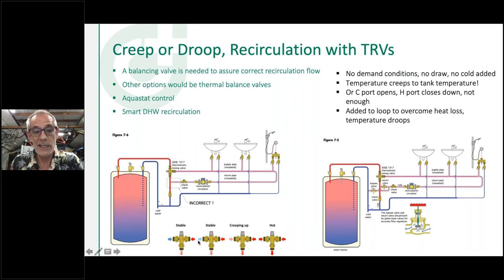Over time, the temperature coming out of the mixing valve creeps up to the same temperature as the hot input. You'll send the valve back saying it doesn't regulate — but it's not the valve, it's the condition. The opposite can also happen: temperature droop, where if there's not enough incoming temperature to compensate for heat loss around the loop, the outlet temperature drops below the valve setting. Two fixes: electrically, put a set-point controller or timer on the pump to shut it off when the loop is warm. Mechanically, add a bypass valve.